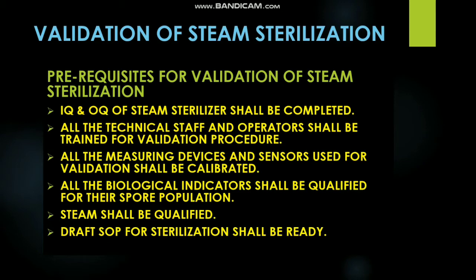Then what are the prerequisites for steam sterilization? If you want to do steam sterilization, these are the prerequisites which need to be fulfilled prior to execution of a performance qualification. IQ and OQ of the steam sterilizer shall be completed and signed off. All the technical staff and operators shall be trained for validation procedures. They should be trained in how the activities need to be executed and what precautions we need to take during performance qualification of the autoclave.